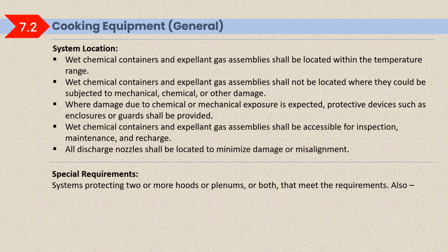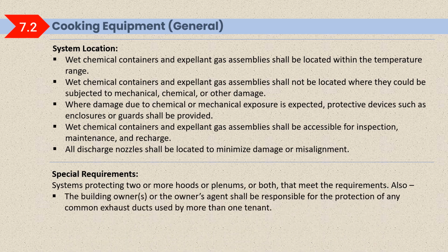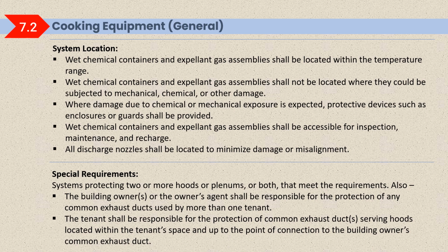Special requirements: a system protecting two or more hoods or plenums or both that meet the requirement. Also, the building owner or owner's agent shall be responsible for the protection of any common exhaust duct used by more than one tenant. The tenant shall be responsible for the protection of common exhaust ducts serving hoods located within the tenant's space and up to the point of connection to the building owner's common exhaust duct. This is talking about the food court type of provision where a master duct is there.